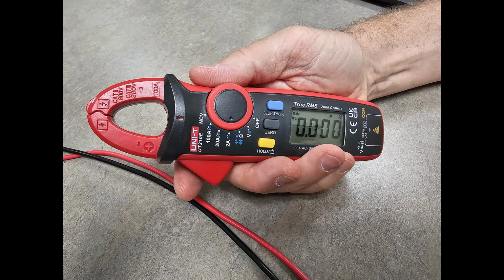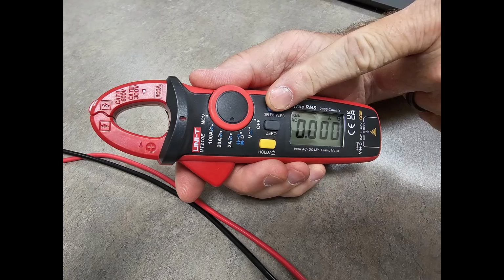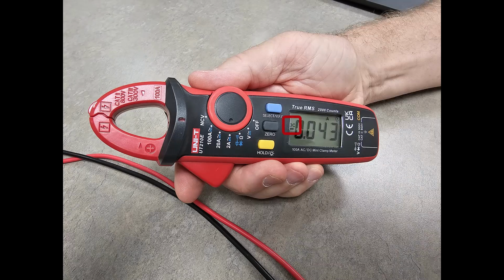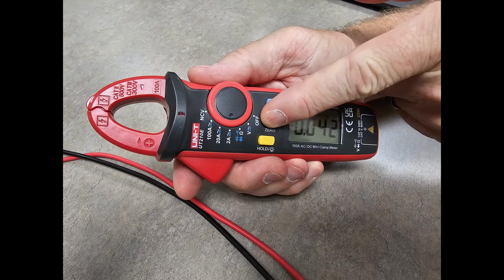The default setting for the clamp meter is AC, so we next press the blue select button to change the setting to DC. Even before placing the meter in position, you may observe some ghost currents in milliamps on the screen. Press and release the 0 button to get rid of these.